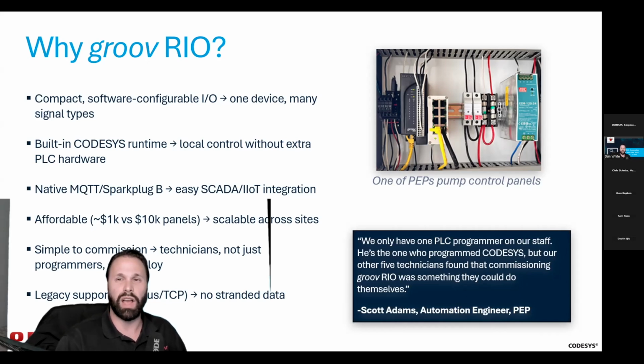Then, of course, you've got a built-in CODESYS runtime license. We license CODESYS on groov RIO for a one-time charge of only $100 per unit. That gives them local control right at the edge without needing a separate PLC panel. The pumps could run locally and automatically based on tank levels, fully independent of the SCADA system right there at the edge.